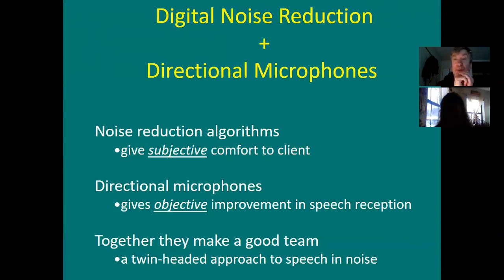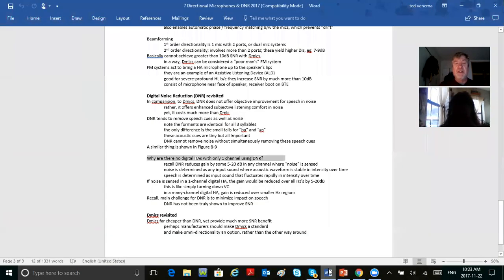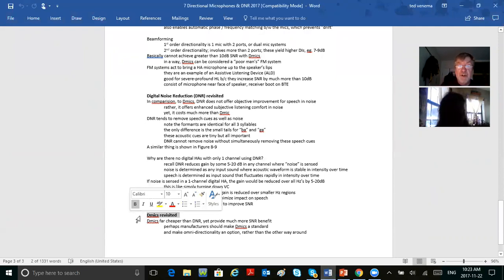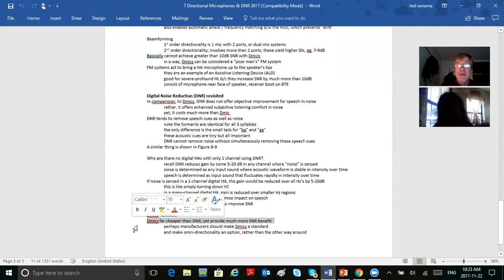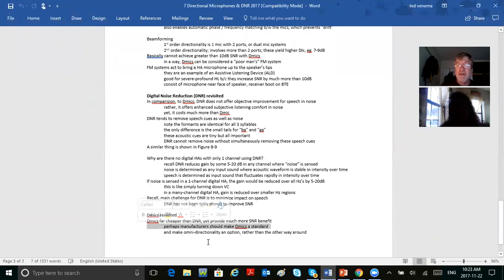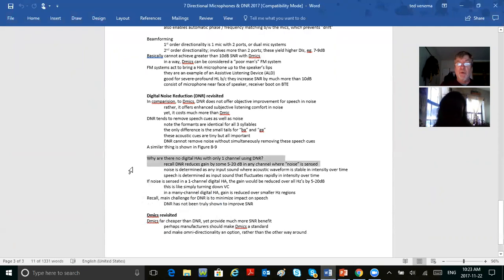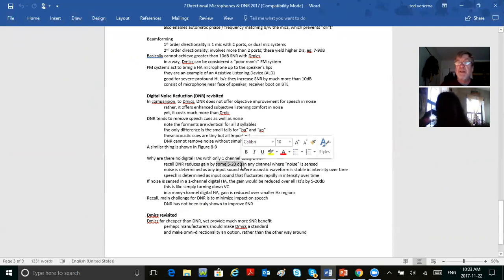Have a good read of chapter 9 in the textbook. D-mics are far cheaper than digital noise reduction, but they provide much more signal-to-noise ratio benefit. Perhaps manufacturers should make D-mics a standard and make omnidirectional an option rather than the other way around. DNR reduces gain by about 5 to 20 dB, and in software you can choose the degree of DNR — mild, average, or maximum.